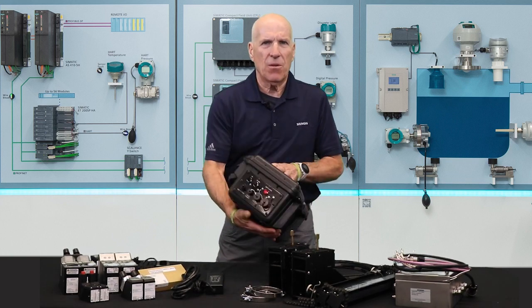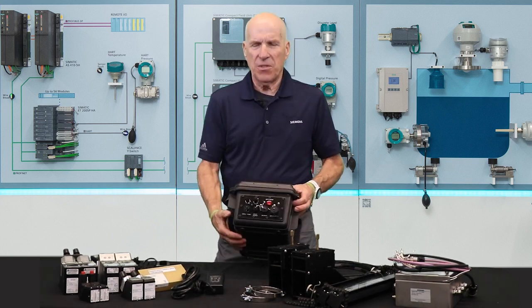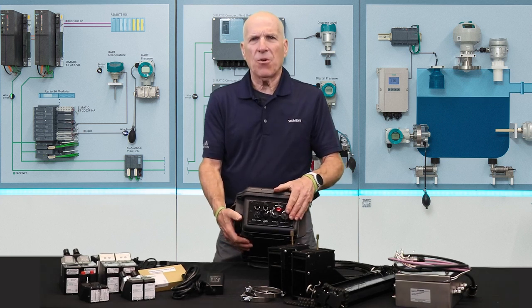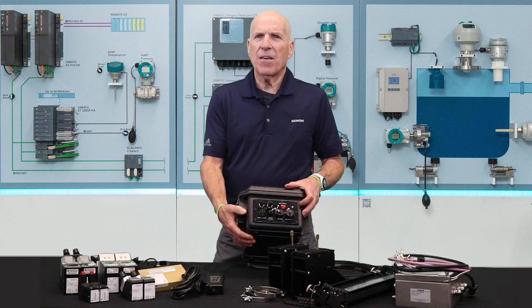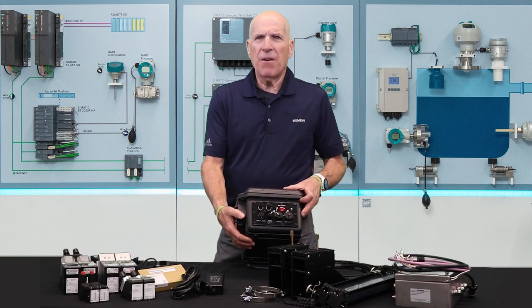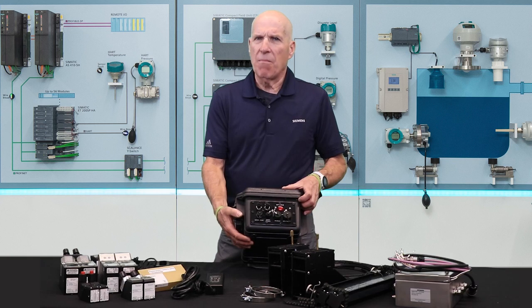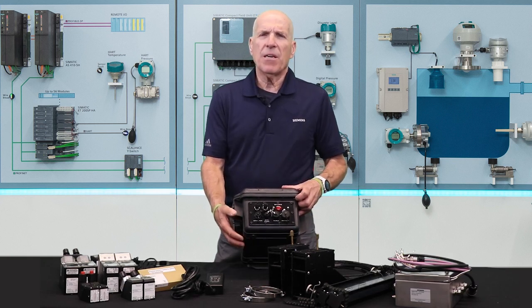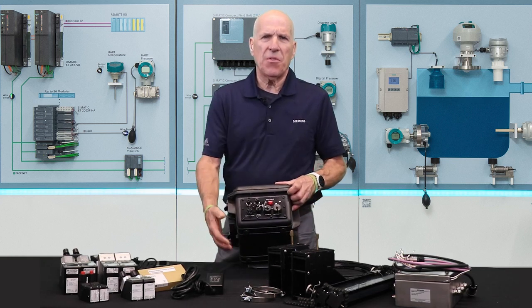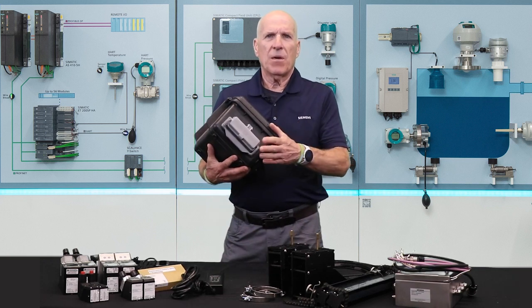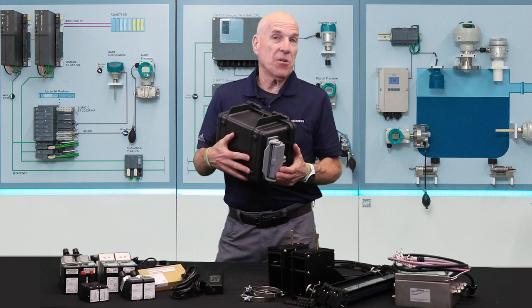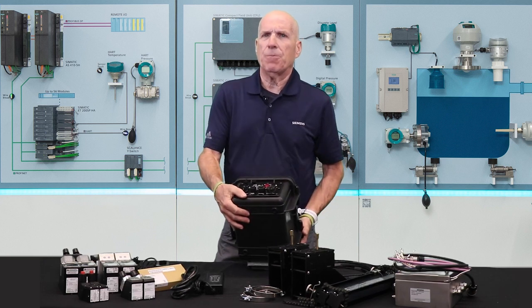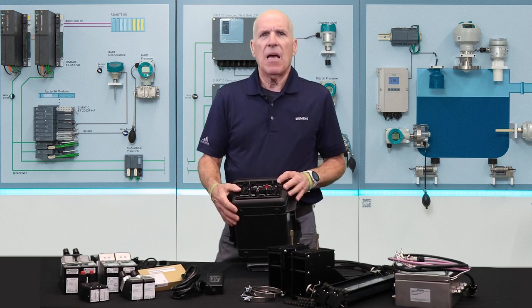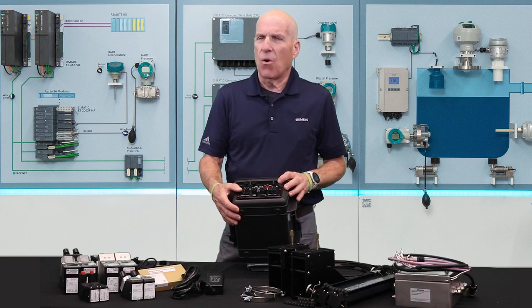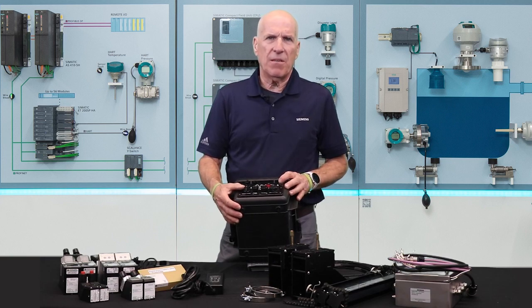The FS290 transmitter is a single-path system with a fixed output and communications arrangement. On the top of the meter enclosure, you'll see the connections for your flow sensors, multiple output terminal, power connection, and communication port. Every FS290 comes equipped with a current, pulse, and relay output, along with Modbus communications. The meter is powered by its rechargeable lithium battery, but can also be operated using an optional power supply and AC adapter connected to mains power. Again, the system label found inside the door will provide the configuration details of your system.